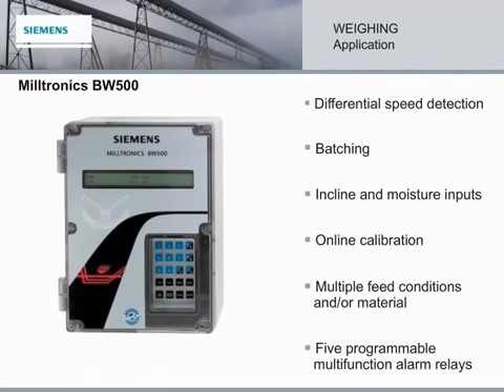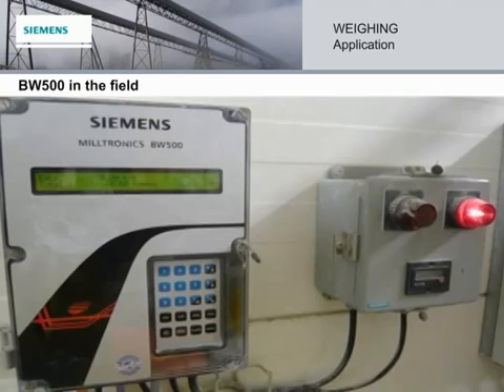The Milltronics BW500 performs sophisticated measurement and flow control functions such as these: differential speed detection and batching, incline and moisture inputs, online calibration, multiple feed conditions and/or material, and 5 programmable multifunction alarm relays. The BW500 is where it all comes together, providing the exact results required from a belt scale system.